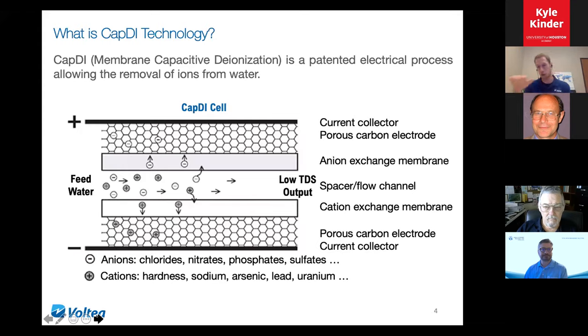This way, as you flow water through and we pull those ions, those minerals, those salts, that TDS out of the water, that's going to give you a low TDS output. One of the things I think is cool about the technology is that because we're using electricity in this manner, we can tune it. You can basically turn up or turn down the current or the power to remove more or less of that TDS.